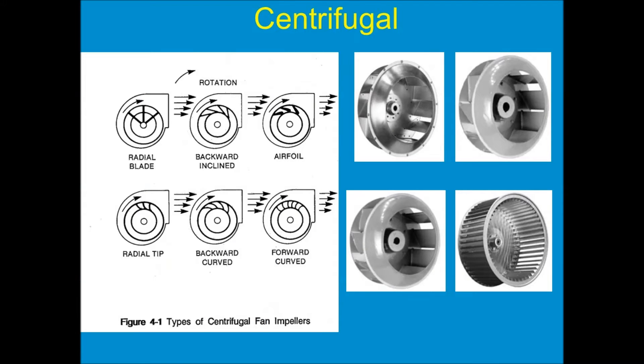There are many different types of centrifugal impellers. Backward incline is by far the most common — it can be flat blade or airfoil blades. There's radial tips, forward curve — the economical squirrel cage type wheel, shown here in the lower right image. There's also radial blade type. It depends on the application, but in each case the impeller is performing the same way.